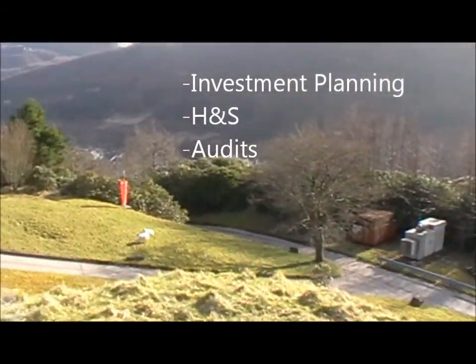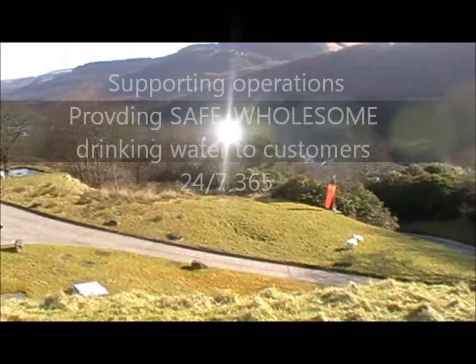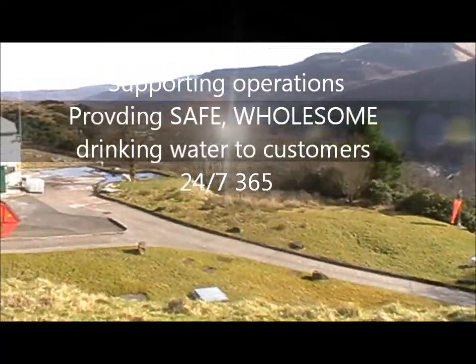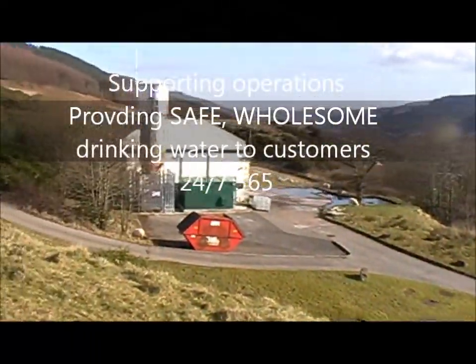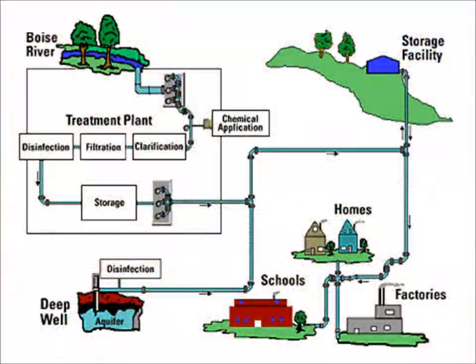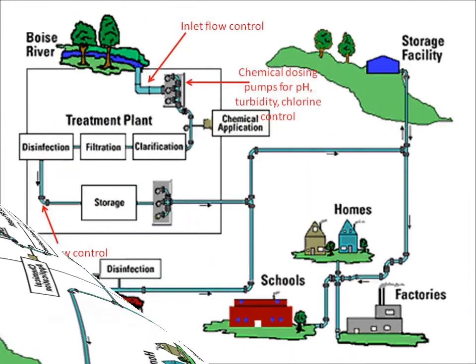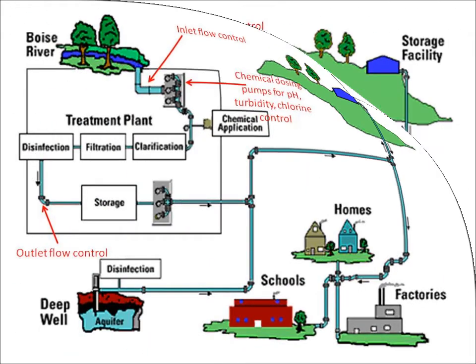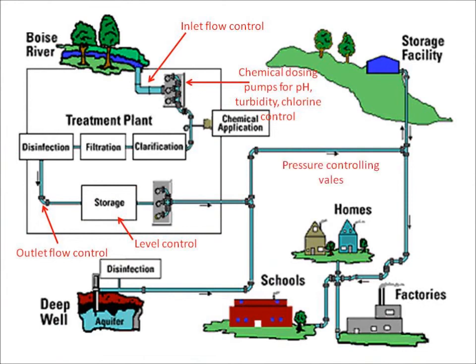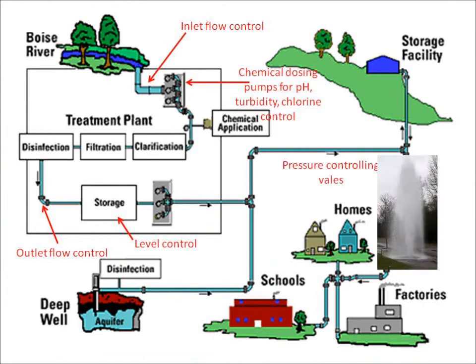My primary goal is to provide safe, wholesome drinking water 24-7, 365 days of the year. In order to provide this level of service and meet strict DWI regulations, we need constant monitoring of our processes, including inlet and outlet flows to meet demand, pH, turbidity and chlorine monitoring, service reservoir levels and network pressures — as drops in pressure could indicate bursts or leaks in the network.